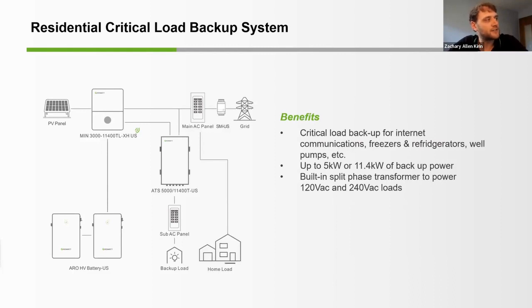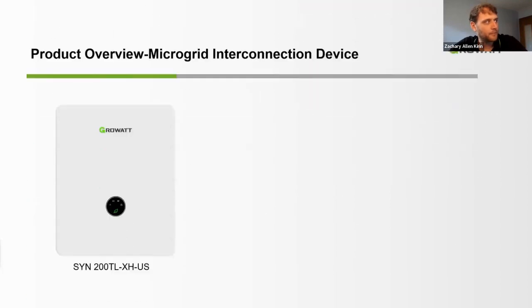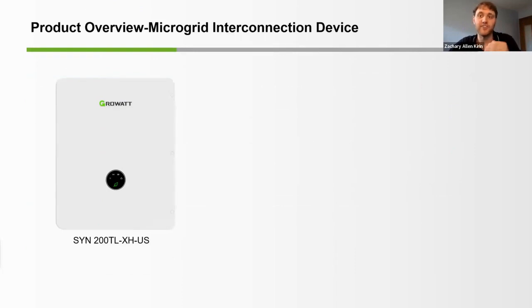The operation of this, again, you need to have the smart meter in order to interface properly with the ATS device. Essentially when the grid goes down, the inverter will sense this, switch over to only powering the load on the backup line, and then power the sub panel, the critical loads, with the energy from the PV array and the battery as well. During normal on-grid operation, the grid can also supply power to the critical loads, to the main panel, and charge the battery. Everything is normal, but when the grid goes down, the inverter switches to its backup function, only powering the backup ATS here. So that was the ATS device interfaceable with the V2 model of the inverter. That is for critical load backup.